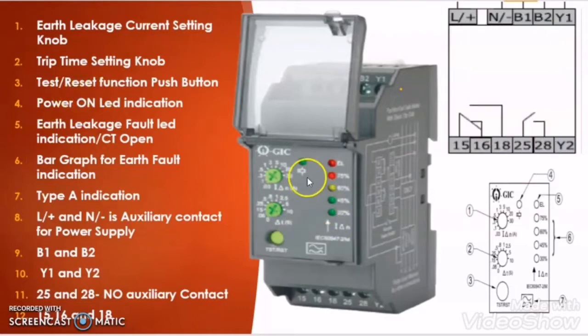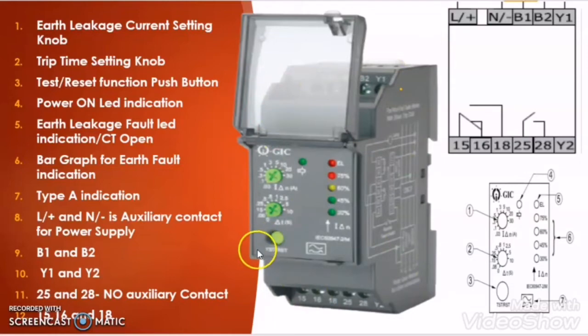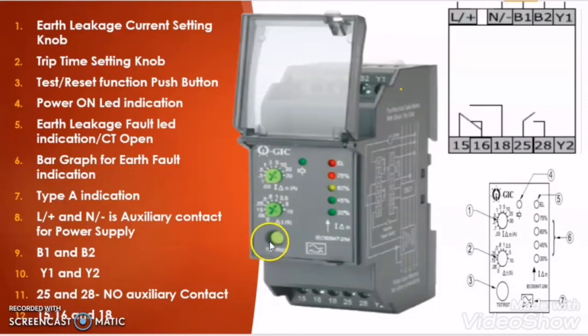The third thing which you will find on the earth leakage relay is a test and reset function push button. With the help of this button you can reset the earth leakage relay. Suppose the earth leakage relay has tripped due to an earth leakage fault — by pressing this reset button we can reset it. Moreover, from the same test and reset button we can check the correctness of our control wiring. In some ELR models the test and reset button are two different buttons, but some manufacturers provide them as one combined button.